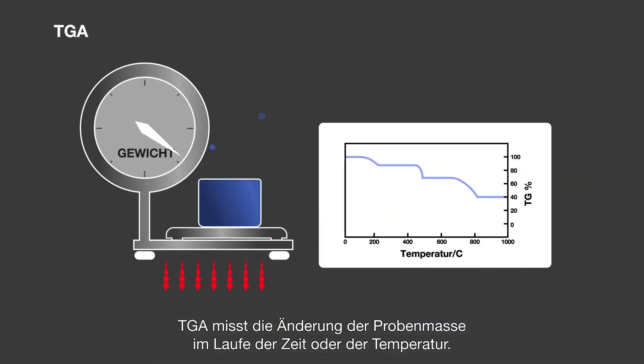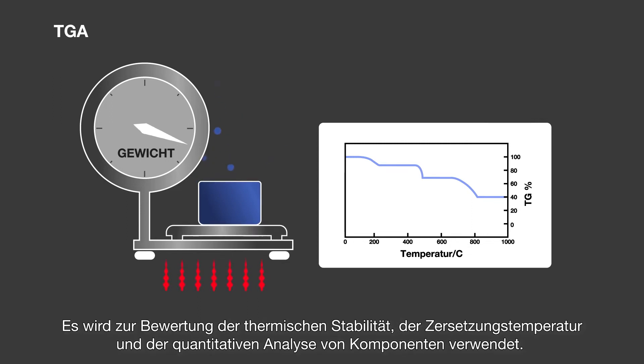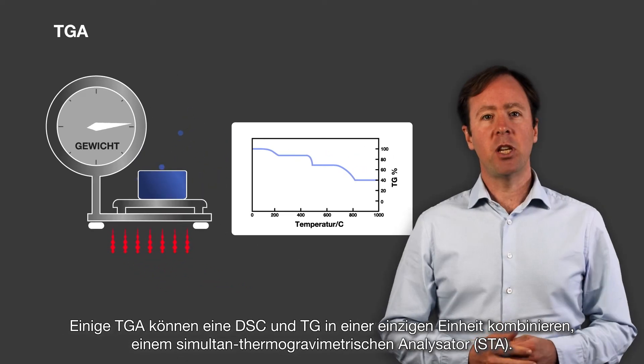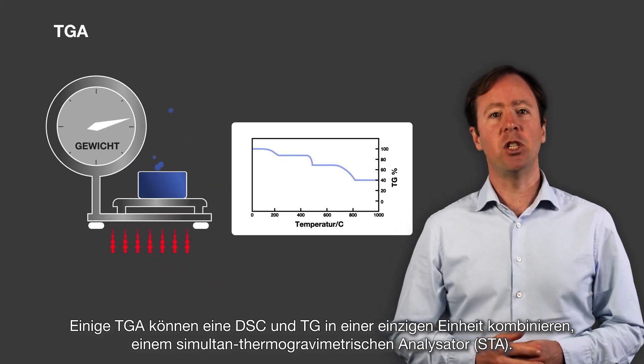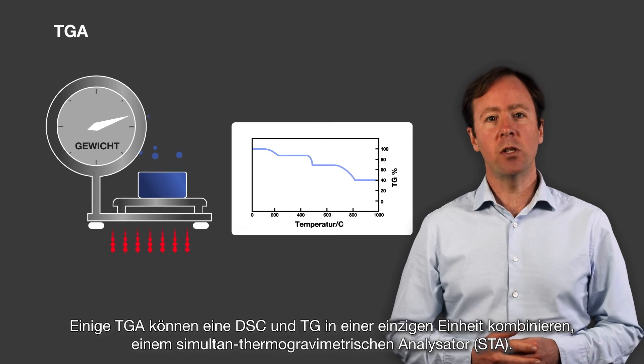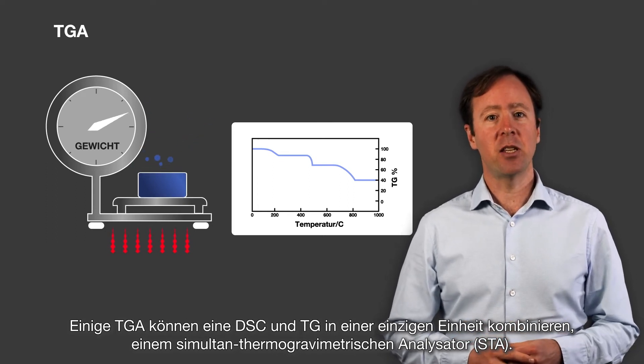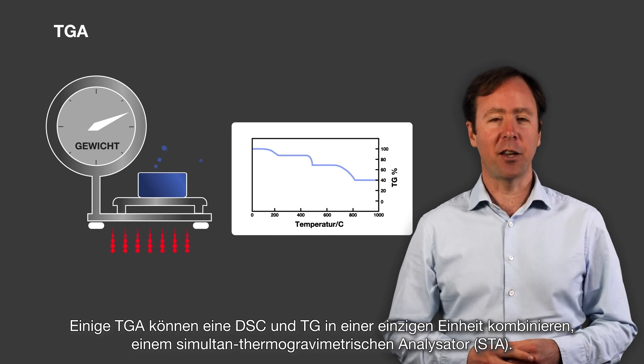TGA measures sample mass change over time or temperature. It's used for evaluating thermal stability, decomposition temperature and quantitative analysis of components. Some TGA instruments can combine DSC and TGA into one simultaneous single unit to give you a STA, a simultaneous thermal gravimetric analyzer.